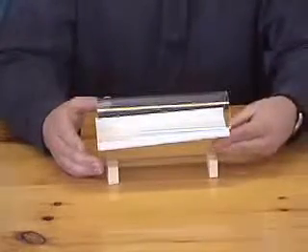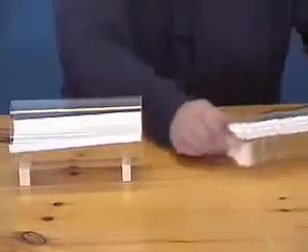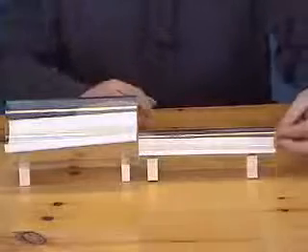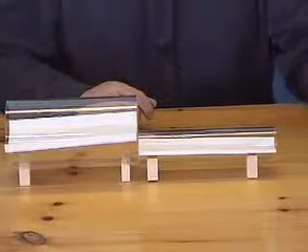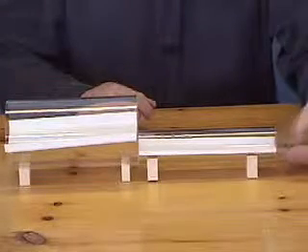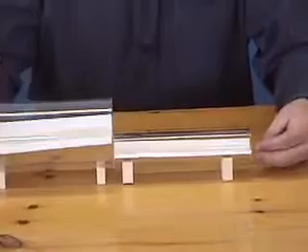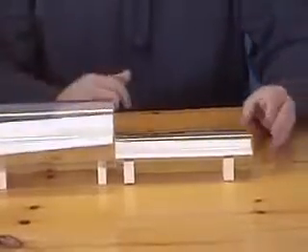Then you'll take the dry side airstream, and you'll run that down yet another one of your heat and mass exchange pipes. After throwing the humid air away again, you'll end up with 1/4 the amount of the air that you started with, and this air will be cooled below the original wet bulb temperature.